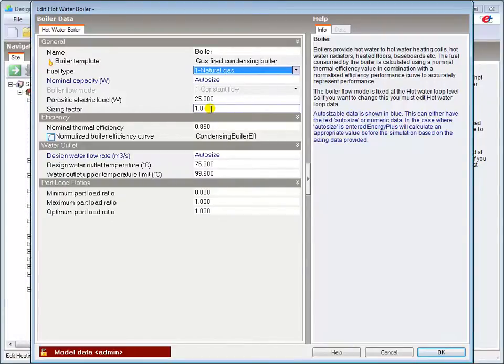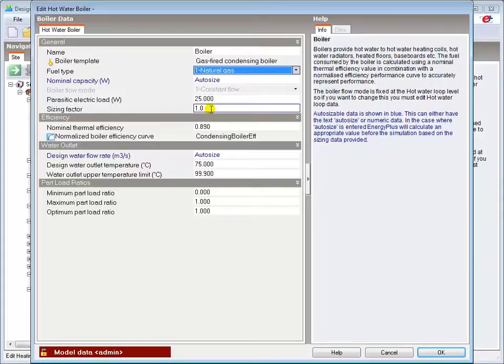The sizing factor is used in multi-boiler loops and allows the user to size an individual boiler to meet part of the design load in conjunction with the Auto Size option if that is used. It adjusts the nominal capacity and design water flow rate of that particular boiler.